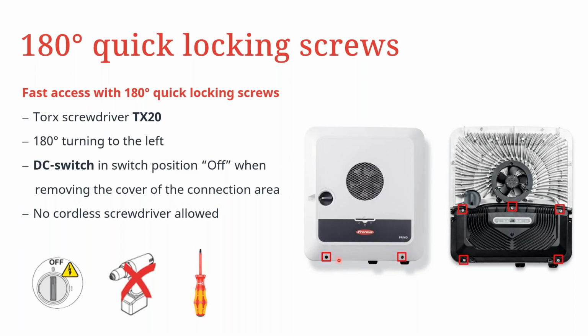We can see that the front cover is secured by 2 screws. Once you release these 2 screws, then you have access to the DATCOM cover, and the DATCOM cover is held in position by these 5 screws, which are also quick release screws. We also have a DC switch that needs to be in the off position. We can see this switch here is the DC switch. This one needs to be in the off position for you to be able to remove this front cover.